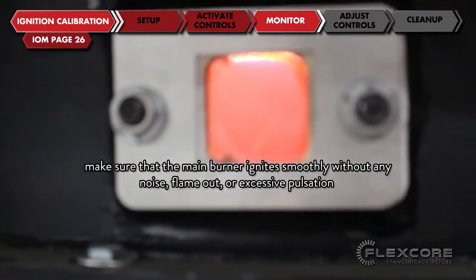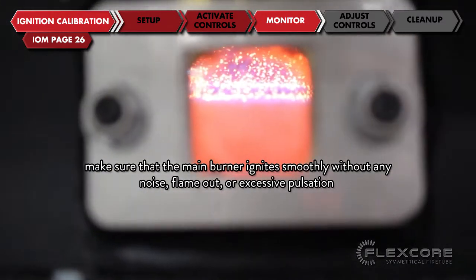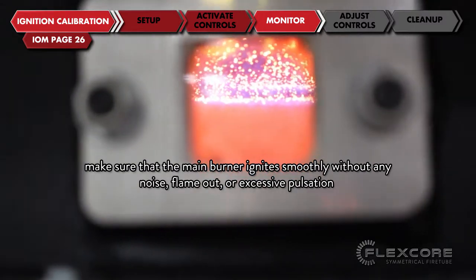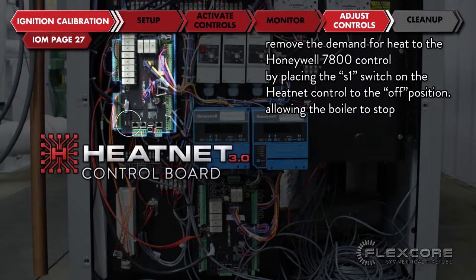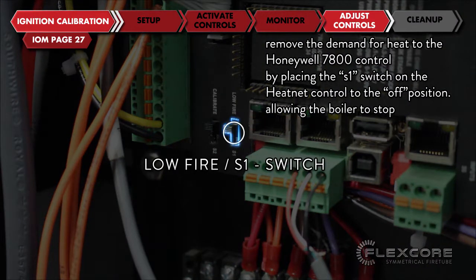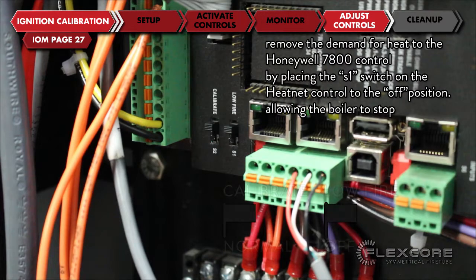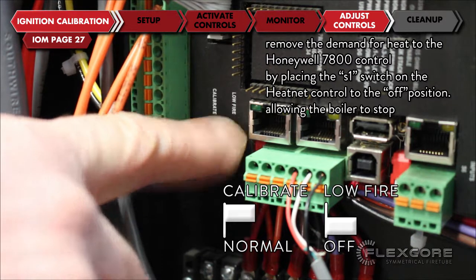Make sure that the main burner ignites smoothly without any noise, flameout, or excessive pulsation. Remove the demand for heat to the Honeywell 7800 control by placing the S1 switch on the heatnet control to the off position, allowing the boiler to stop.